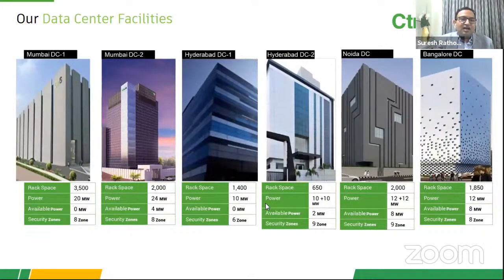On the extreme right left one, we have a Mumbai data center. It's data center 1, with 3,500 racks already filled in. Mumbai data center 2 has 2,000 racks, 24 megawatt. Earlier we had 3,500 racks and 20 megawatt, but the newer one got built with much lesser rack capacity, because power density is increasing. With 24 megawatt, hardly any power is left. Then Hyderabad DC1, DC2, Noida DC1, and Bangalore, 12 megawatt kind of facilities.